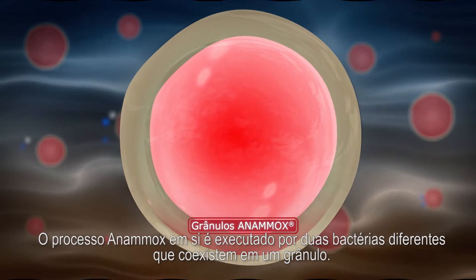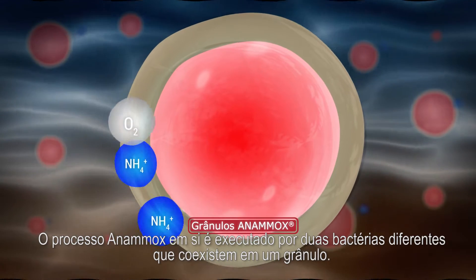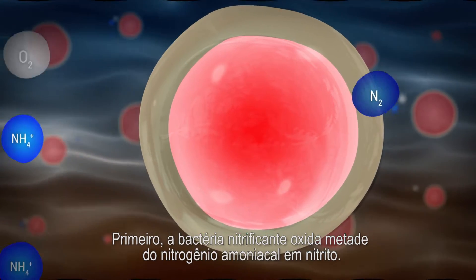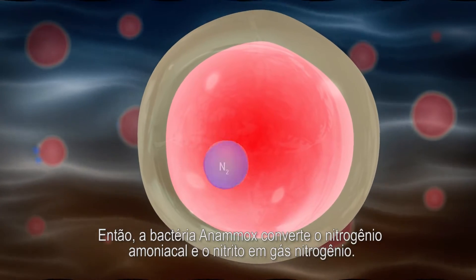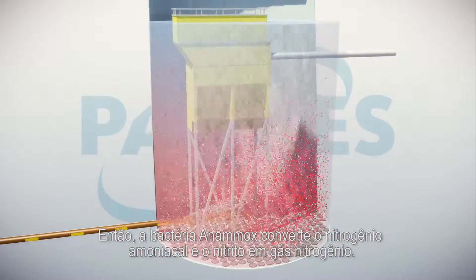The Anammox process itself is executed by two different bacteria which coexist in one granule. First, nitritation bacteria oxidize half of the ammonium to nitrite. Then, Anammox bacteria convert the ammonium and nitrite into nitrogen gas.